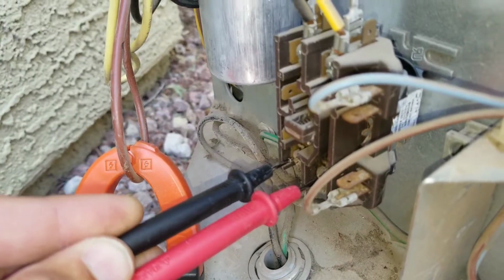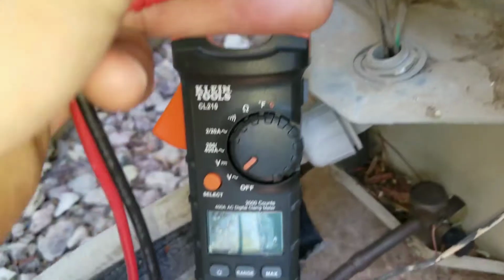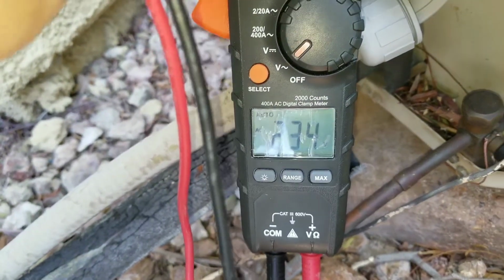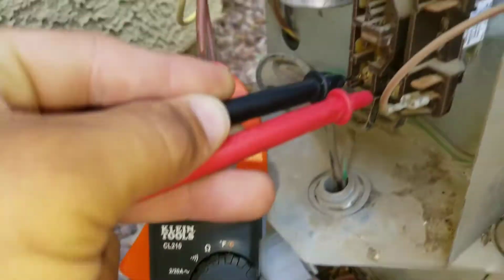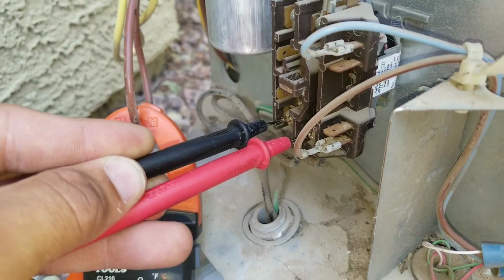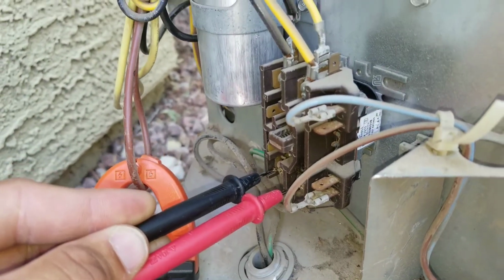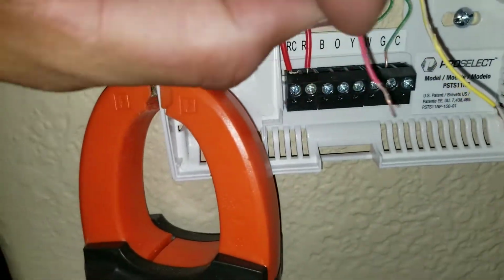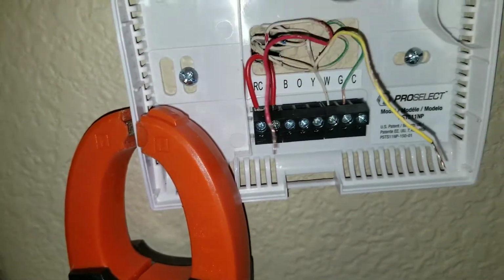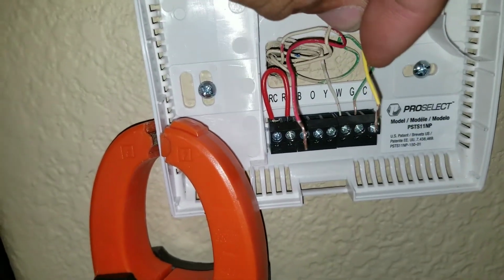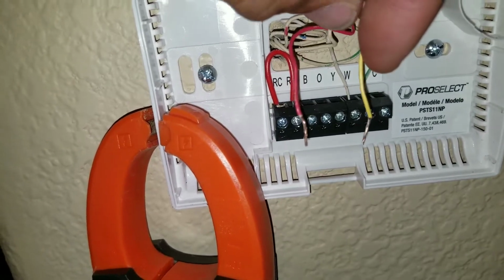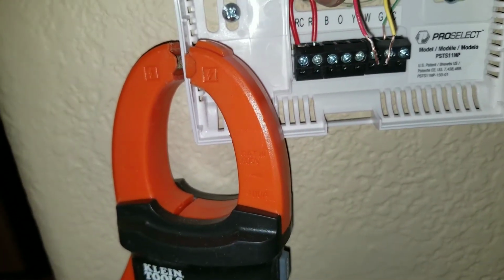This is my line coming in. So I have my voltage, 235 volts, coming into my contactor, so we're having an issue on my low voltage side. So here I've pulled my lead coming off of my R terminal. This is my lead coming from my Y terminal, and basically I'm going to try to jump it.